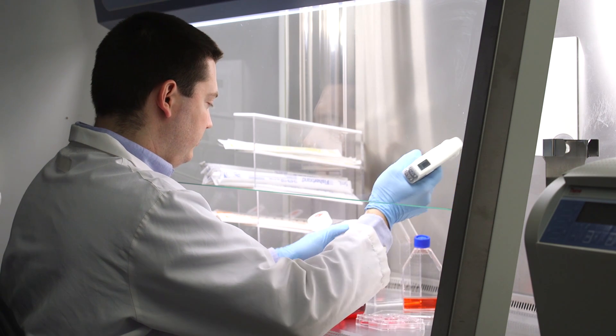Another myth tells us that biosafety cabinets should be left on 24 hours a day. Lots of old manuals say so, but for perspective, one manual from the 1960s suggested using smoke from your cigarette to test the biosafety cabinet air flow. Since modern protocols include a thorough surface decontamination before beginning work, today's common sense suggests running a cabinet only when needed, saving energy costs and prolonging motor and filter lifespans.